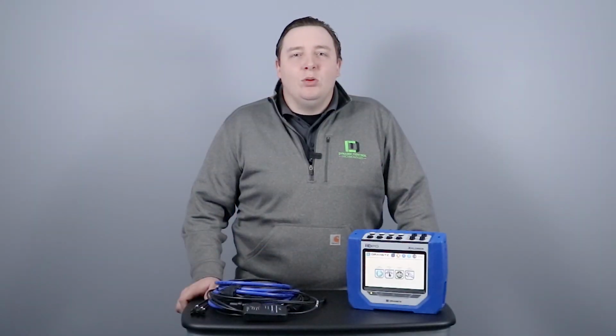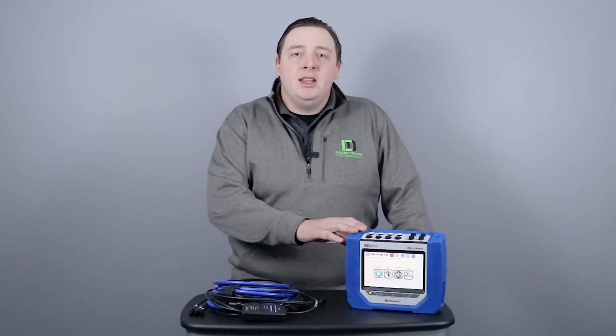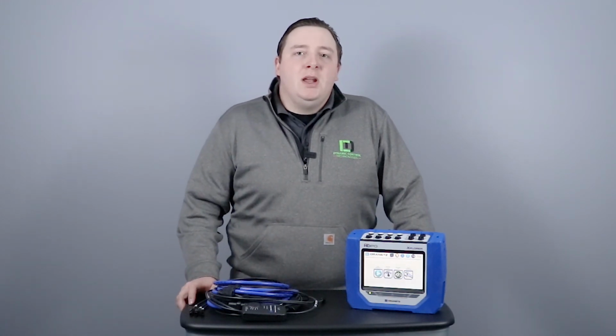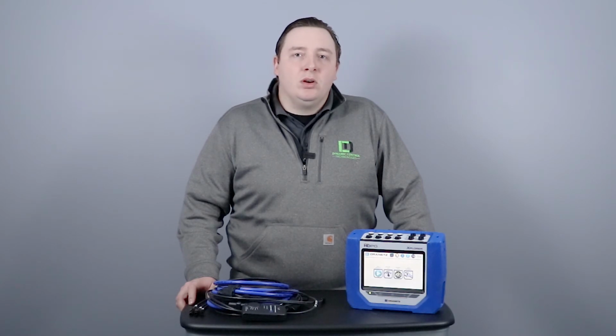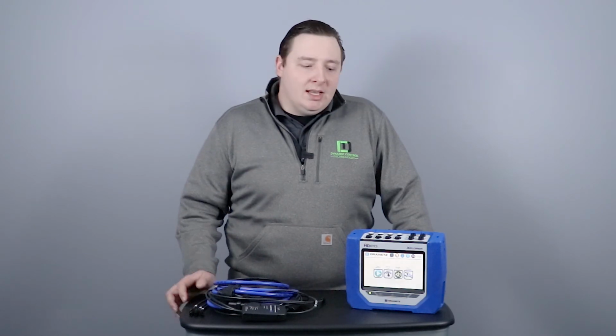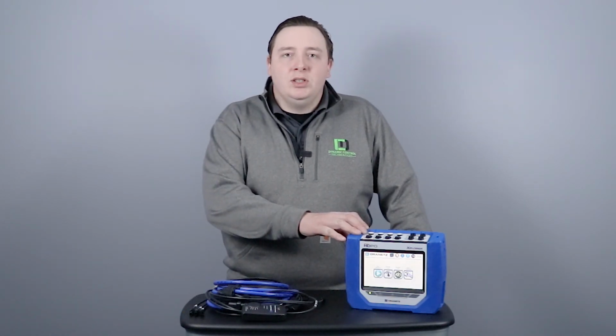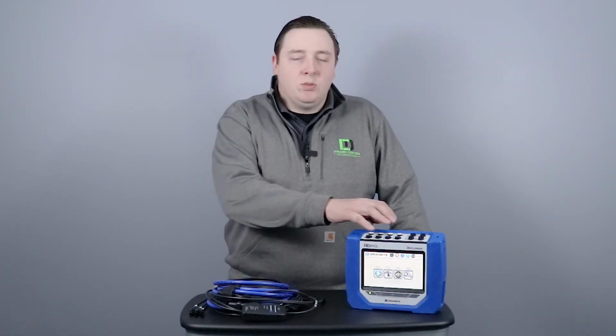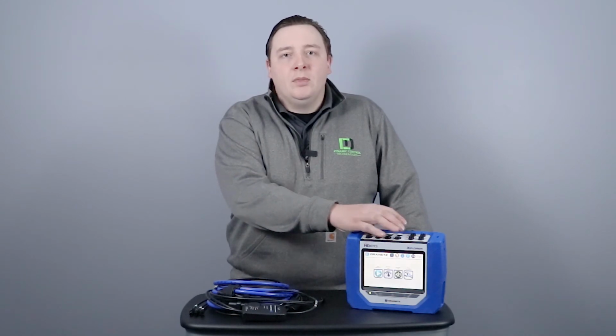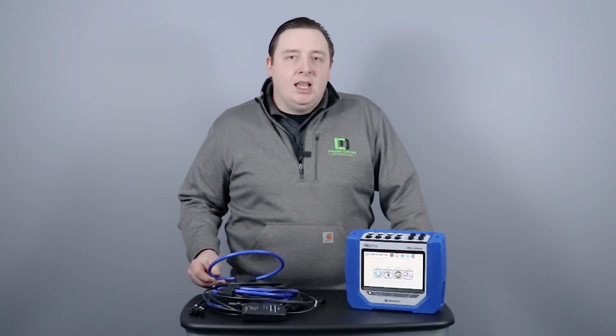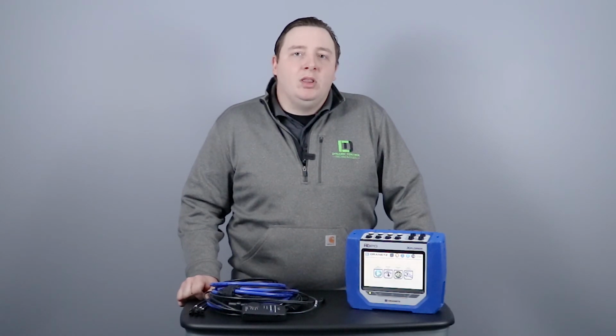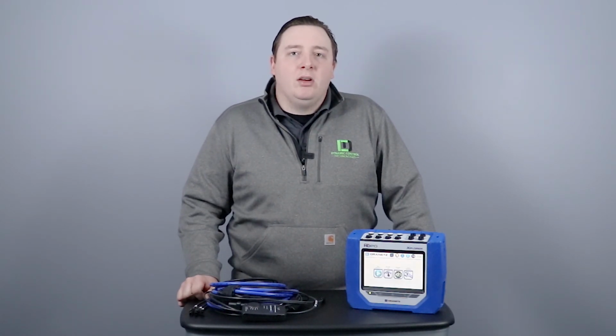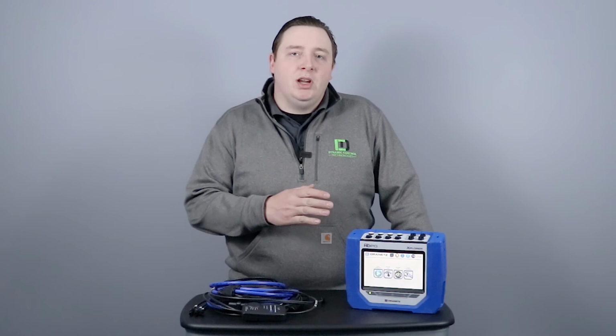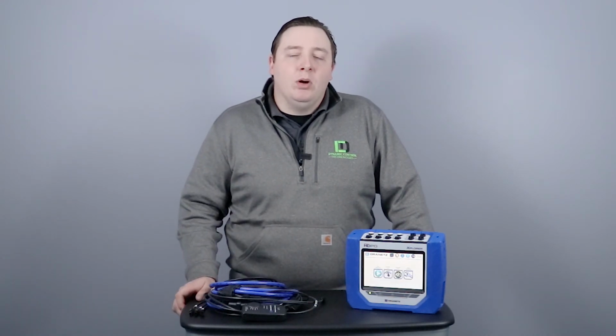One of the most advanced tools we have here at Dynamic is the Dranetz HDPQ Explorer. This meter functions as a power quality analyzer, energy monitor. We can test motors as well as meter for harmonic distortion. It's able to utilize its 4 channels of AC or DC voltage input up to 1000 volts as well as its 4 channels of current. We utilize 6000 amp CTs, which allow us to be able to give customers the flexibility of metering and identifying issues from their main switchgear all the way down to a pinpointed piece of equipment.